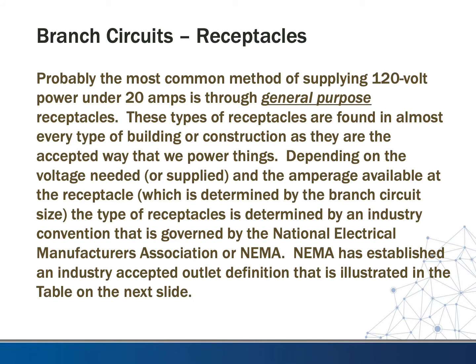The most common method of supplying 120-volt power under 20 amps is through general purpose receptacles, found in almost every type of building as the accepted way we generally power things. Depending on the voltage needed and the amperage available — determined by the branch circuit size — the type of receptacle is determined by an industry convention governed by the National Electrical Manufacturers Association, or NEMA. NEMA has established an industry-accepted outlet definition illustrated in the table in the next slide.